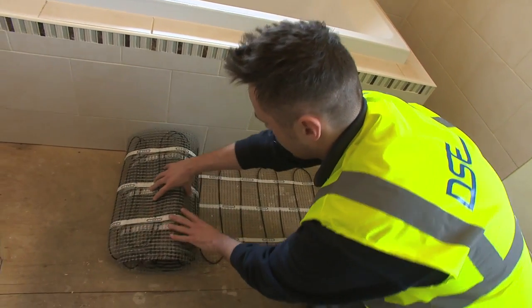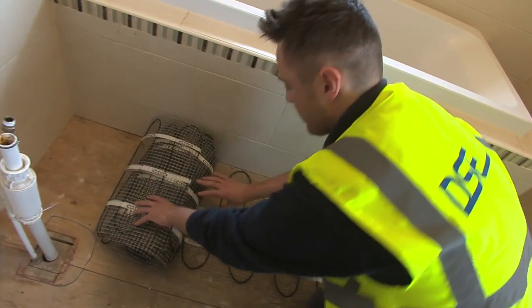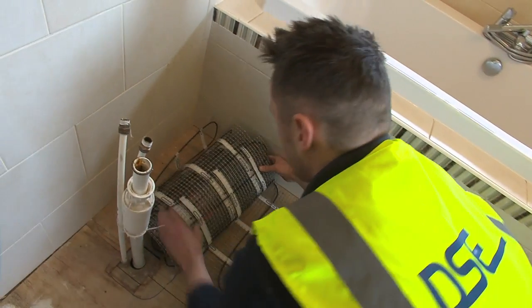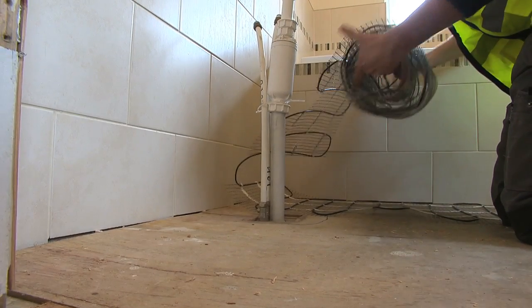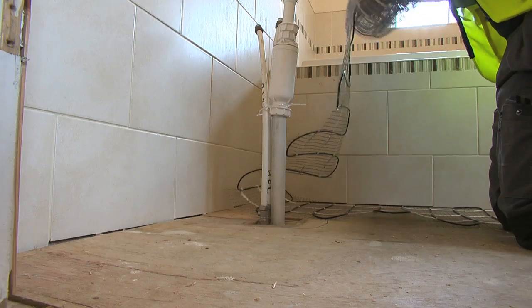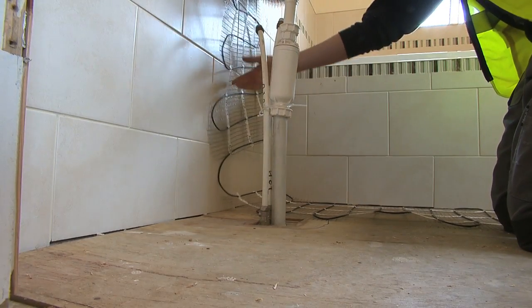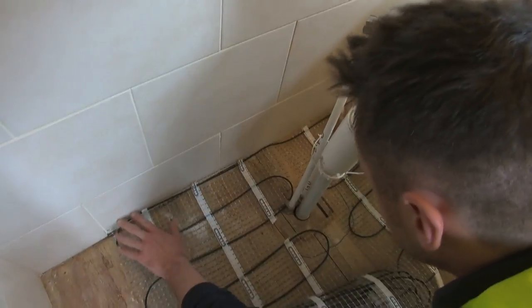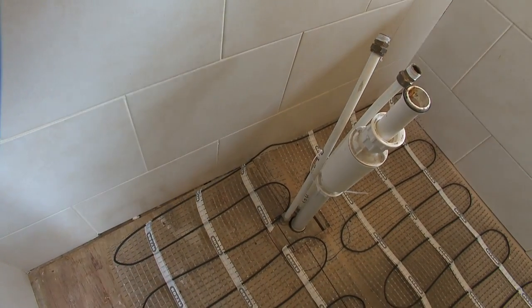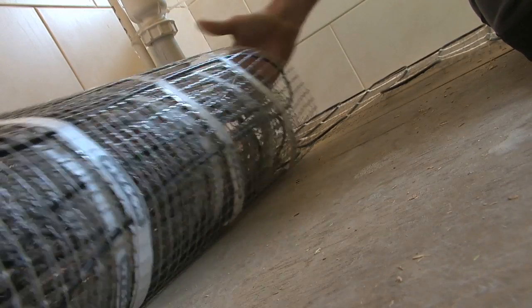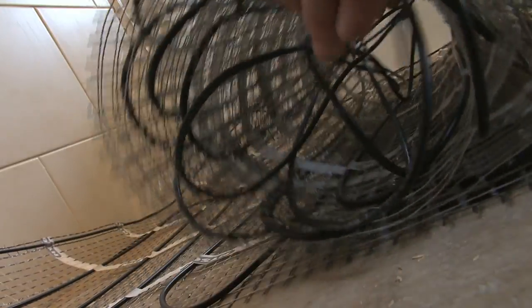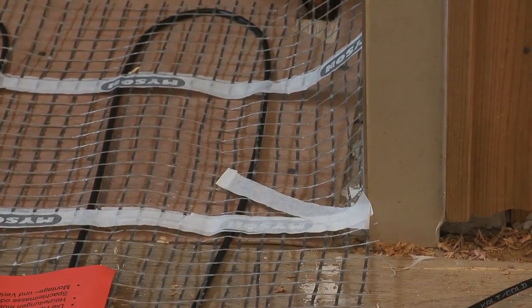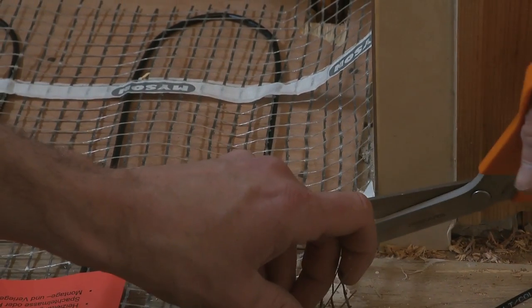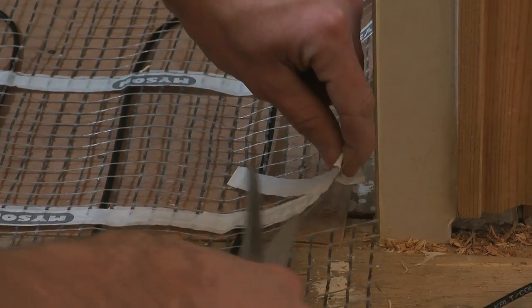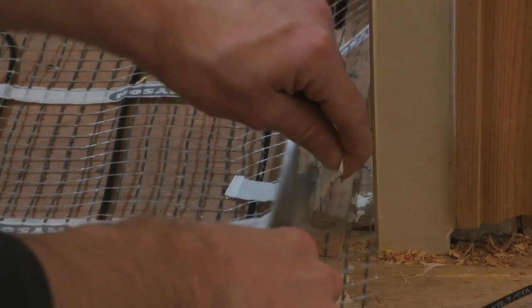But first you need to make sure the surface where the mat will be laid is clean and free from dust or grease. Start to roll out the mat onto the area you are installing. Remember to allow 100mm distance from the wall. You must also make sure that the grey cables are not touching or crossing each other, and that they are at least 40mm apart from each other. If the mat is too long, it can be cut to size, leaving one edge attached, folded over 180 degrees, and then you can continue rolling it out. If it is still too long, you can cut the cable loose from the netting. Please be aware you must only cut the fibre netting and never cut through the heating cable.